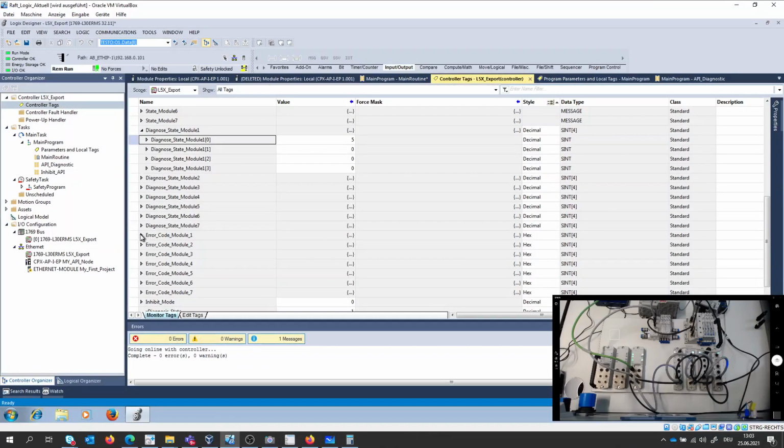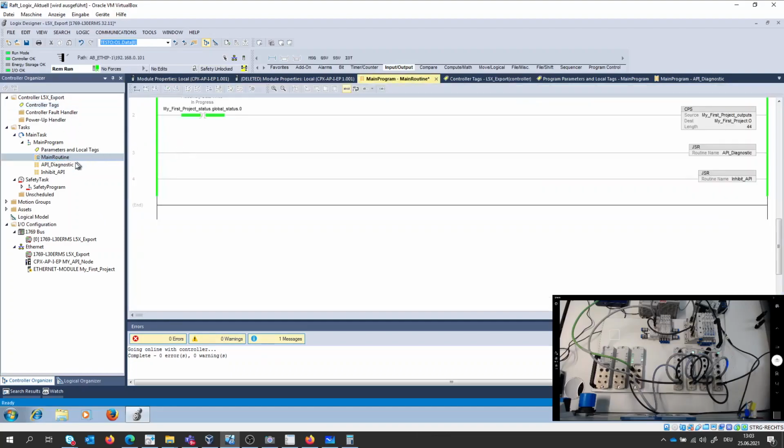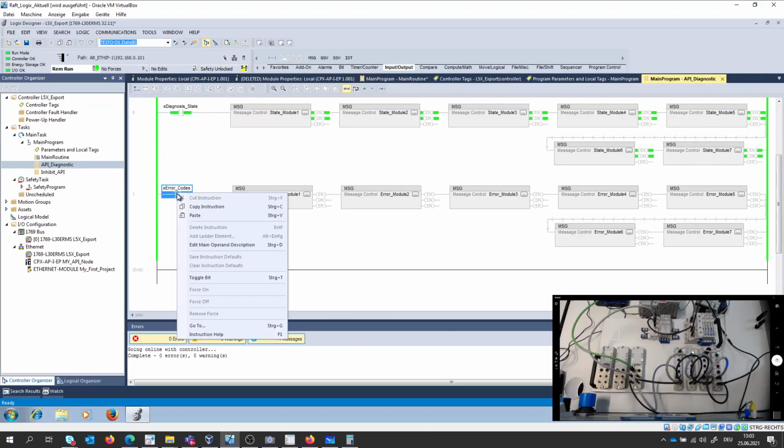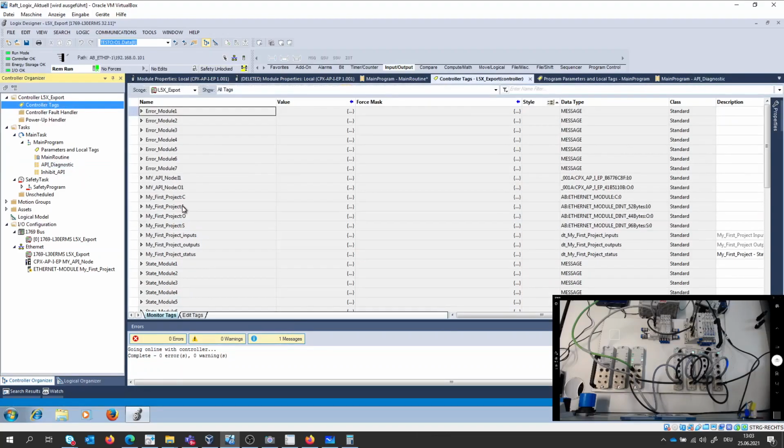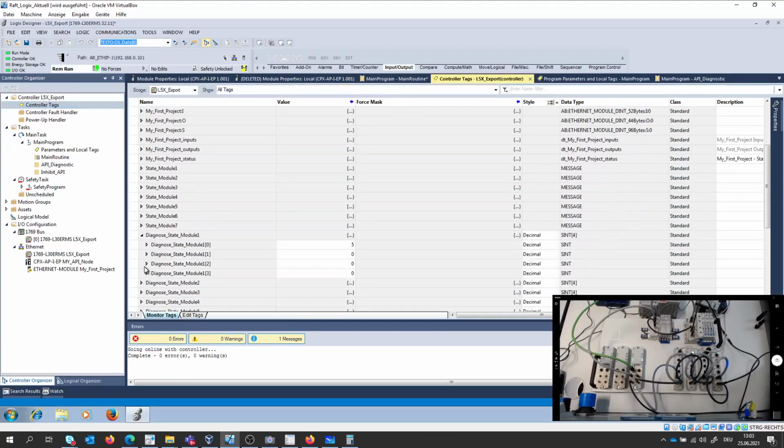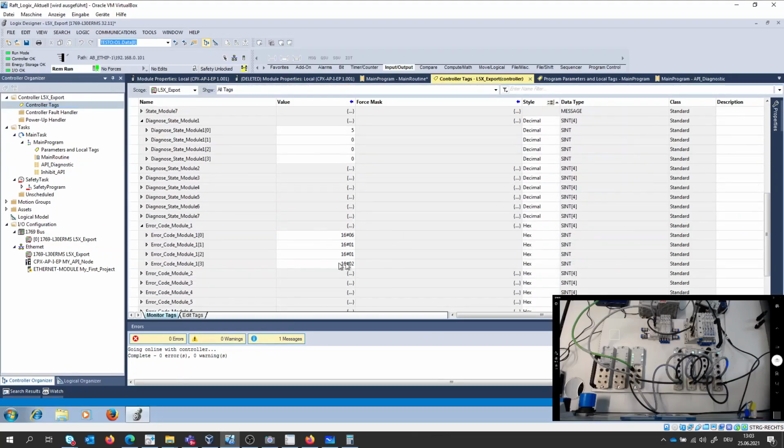If I'm going now to the error code, the error code of module 1 is not executed till now. My mistake. I'm executing it now. And then I'm getting also the module code. And I'm seeing here everything is fine. This is exactly the message if you go in the manual for load supply is missing.